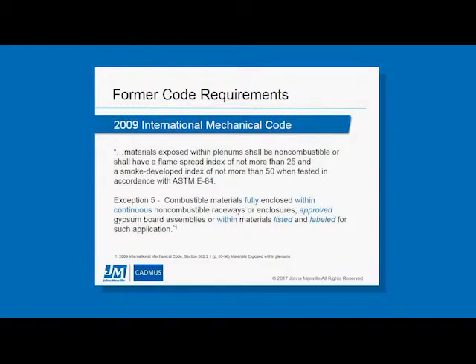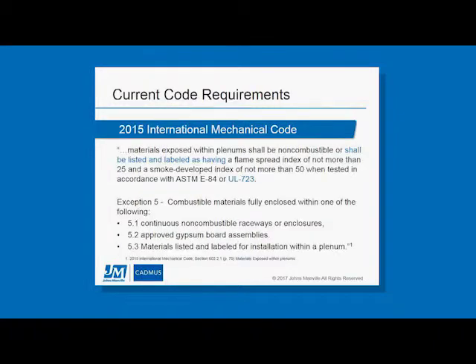As we move forward into 2015, emphasis is placed on listing and labeling. So now it's in the primary paragraph of that section of code, and continues to be in exception number 5, where materials installed within a plenum space have to be listed and labeled for that application, in addition to having that 25/50 fire hazard classification rating.